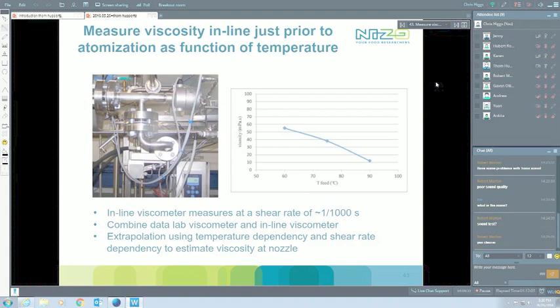time scales there. But what we do have installed in the system is an inline viscometer, where we can actually measure the shear rate. It measures only at a single shear rate, at about 1000 per second, but we can measure as a function of temperature. So combined with the data from the lab, we can extrapolate and see what it would be at a given condition when we're atomizing, and we assume a shear rate of maybe 100,000 per second.